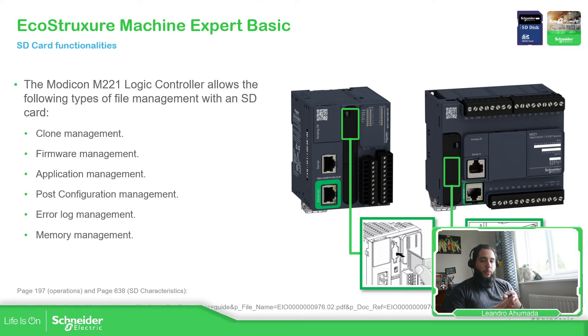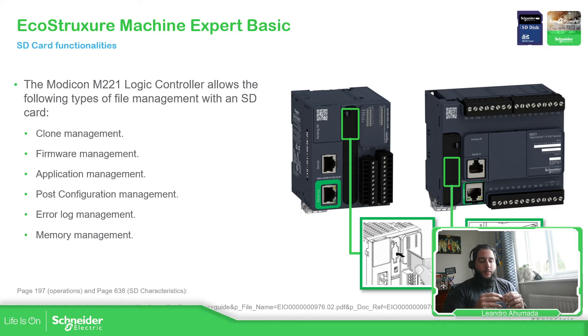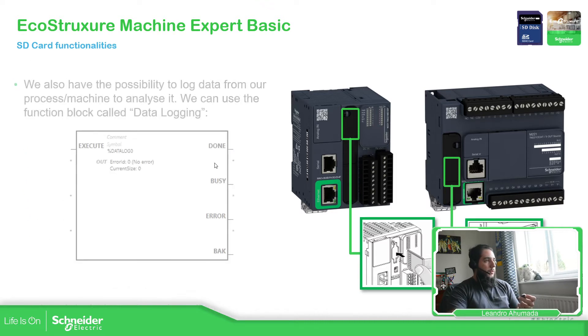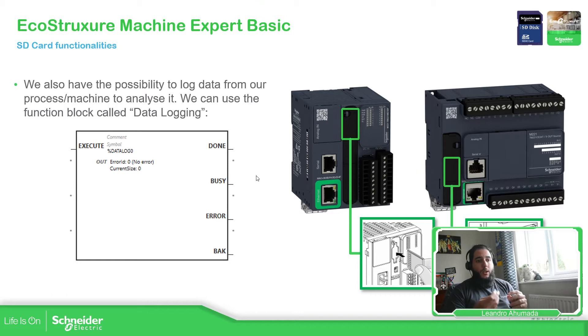We also have the possibility to see errors based on the program we have on the PLC — by mistake or something else. We can upload from the controller into the SD card and see the errors list. We can also use memory management — using the SD card to put on the controller and then retrieve the actual values. And the last functionality is data logging: we can log data into the SD card so we can retrieve it and view it on our laptop.